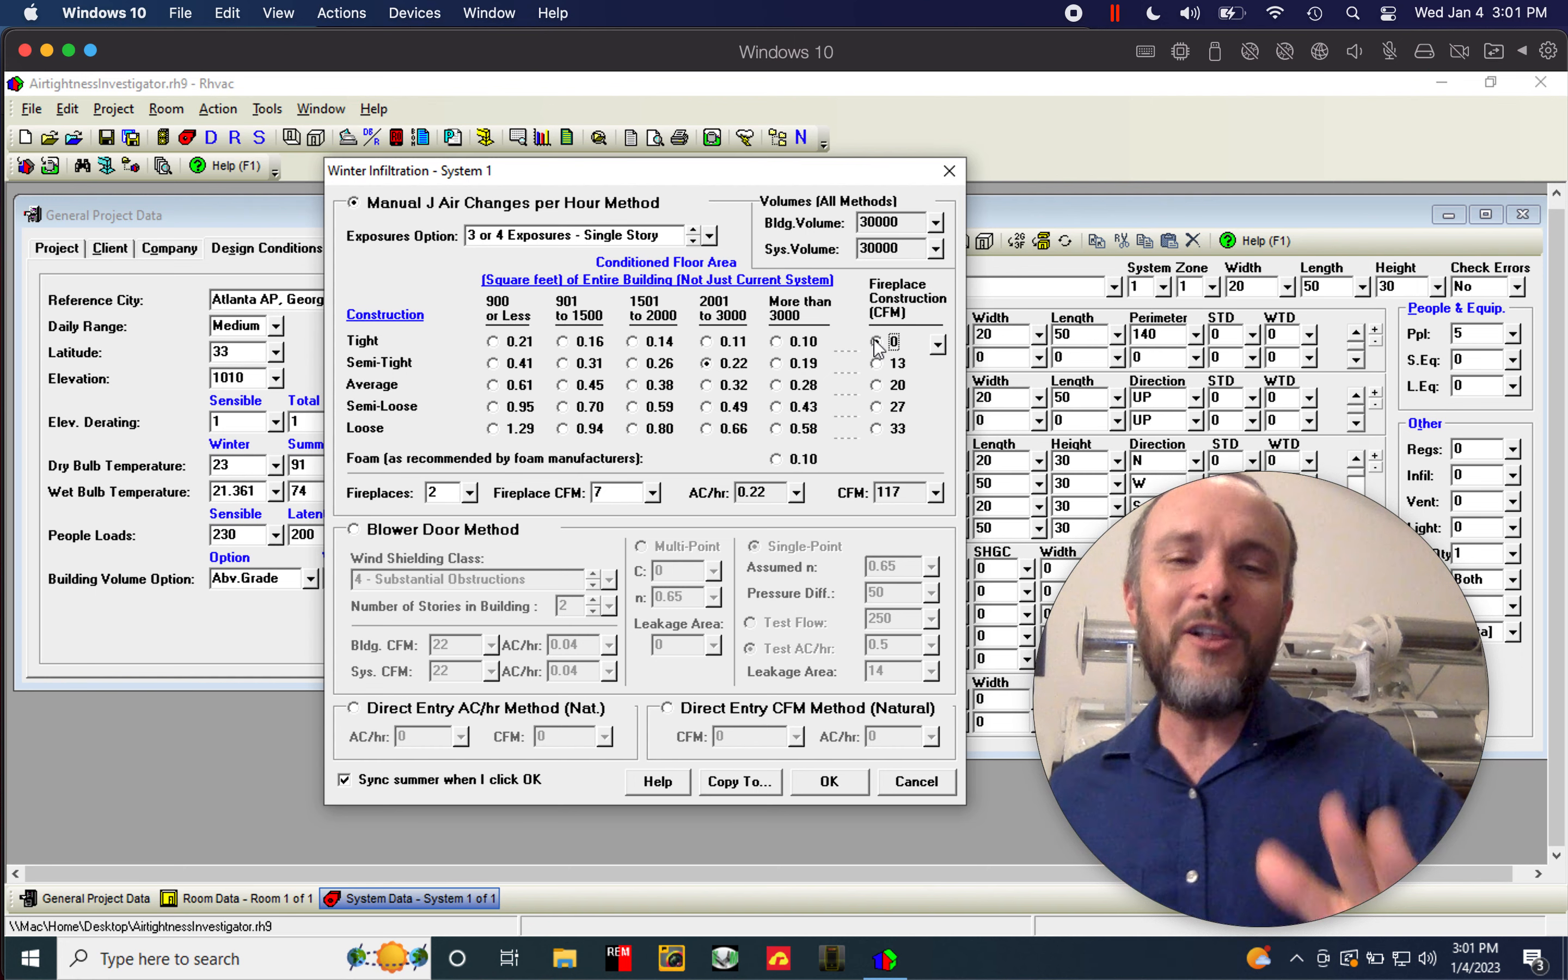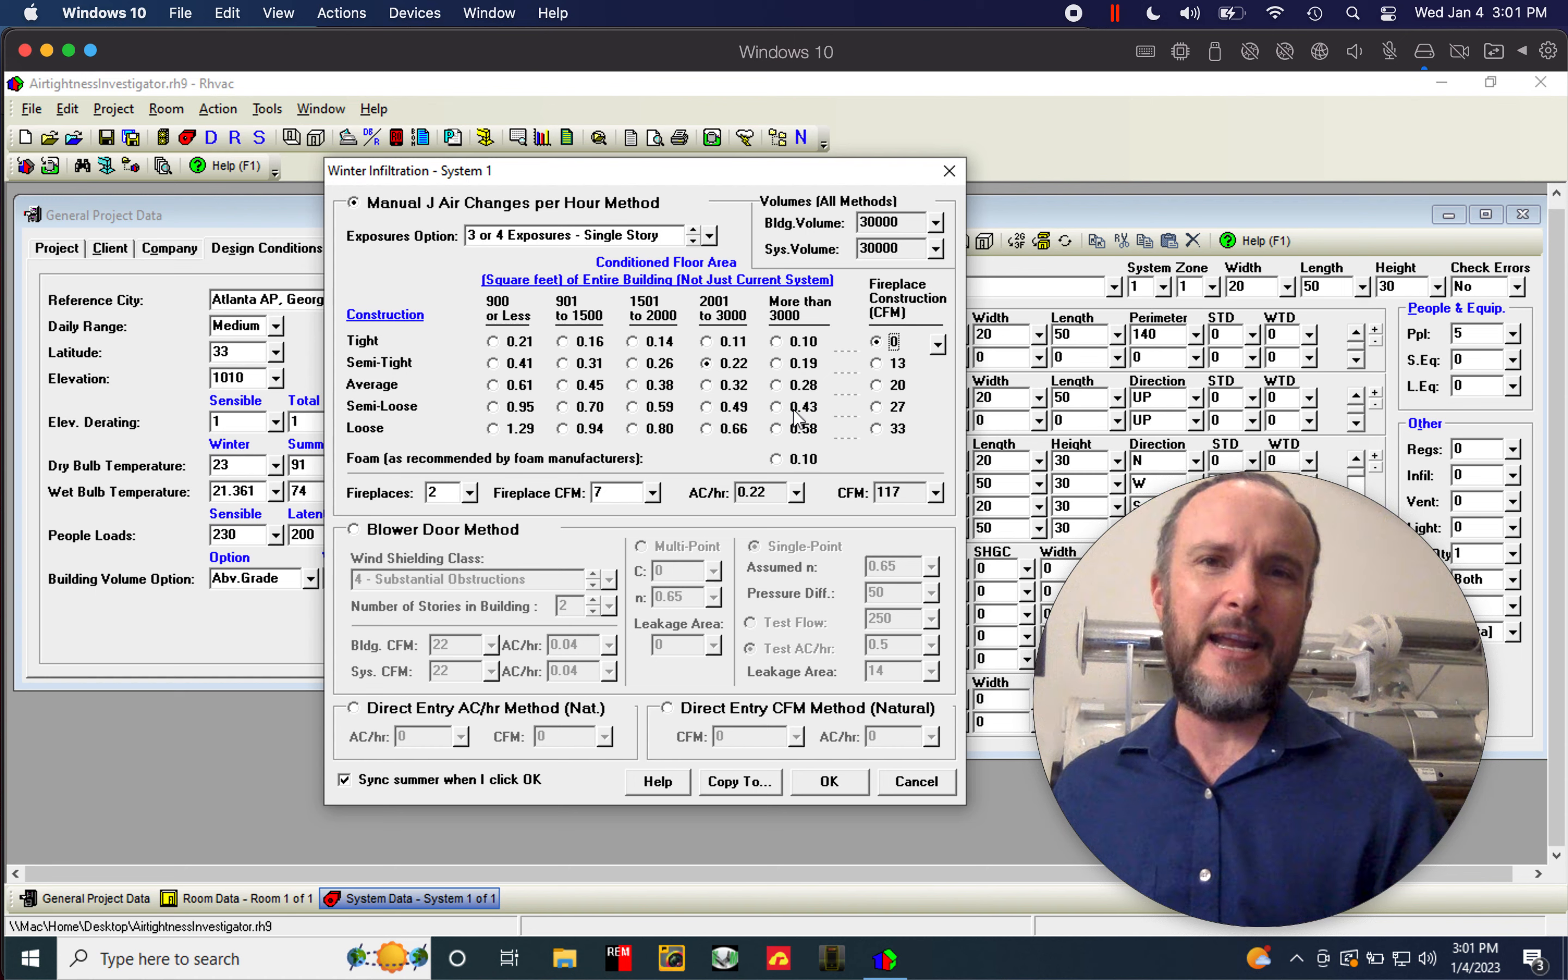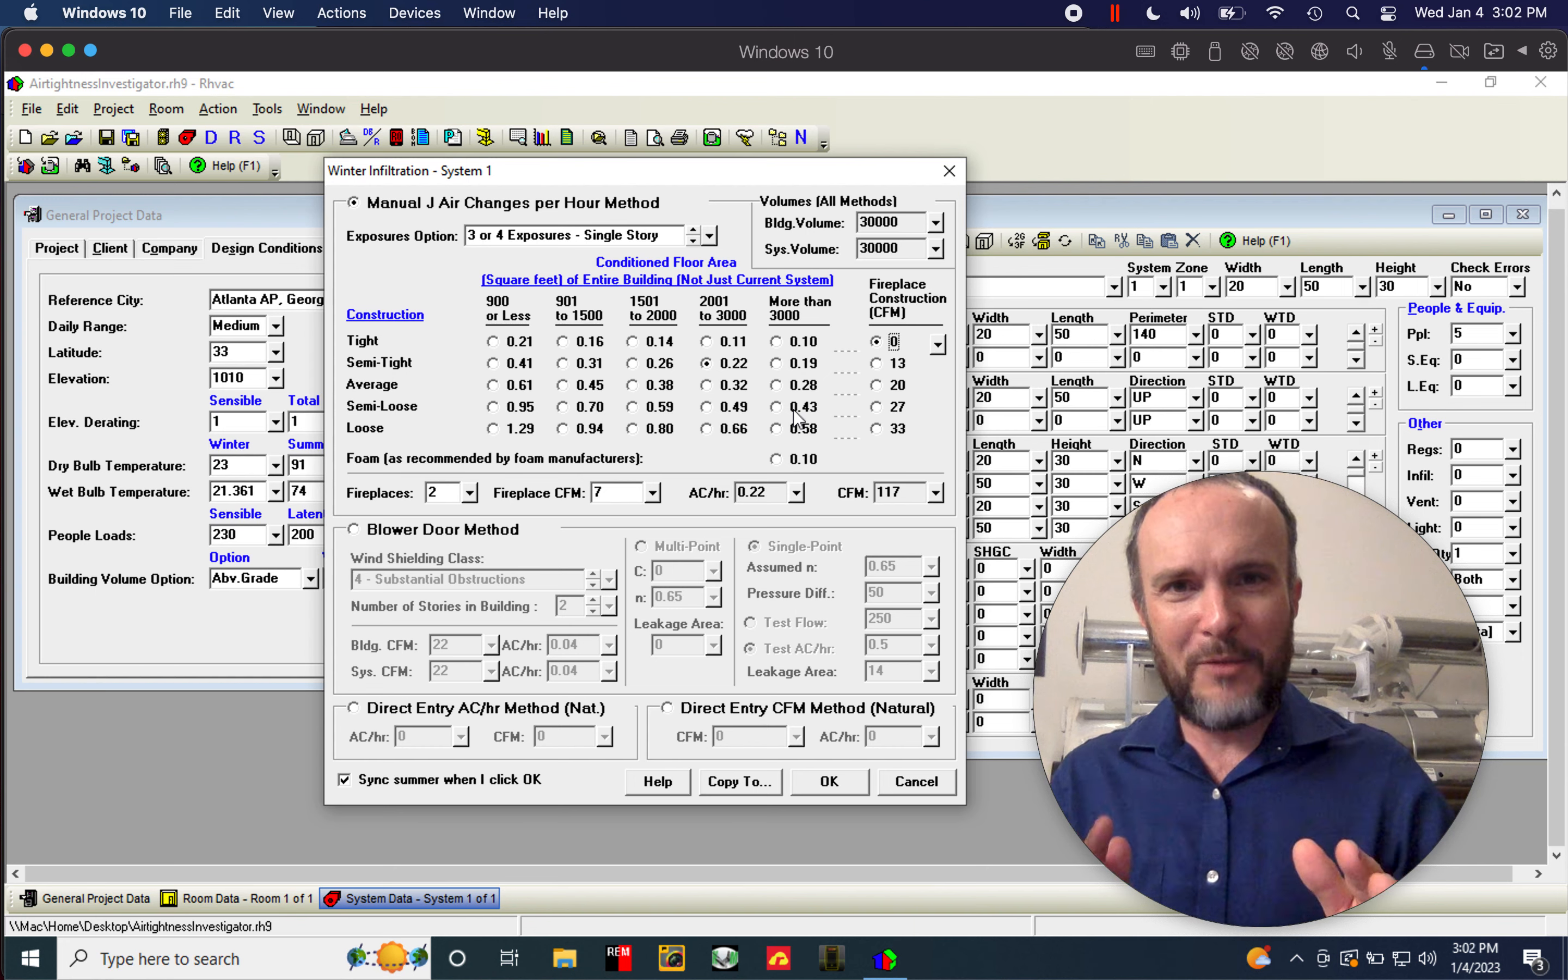Okay. So all of this is to say that I would not trust this top section at all when you're working with the kind of clients who watch this channel, who are really trying to get a very healthy, very airtight, very comfortable and long lasting and all the nice things, quiet home. If you're doing an existing home, do a blower door test, don't assume one of these weird default values. And also this fireplace calculator, I don't even, it's total garbage in my opinion. So I hope that this has helped you.